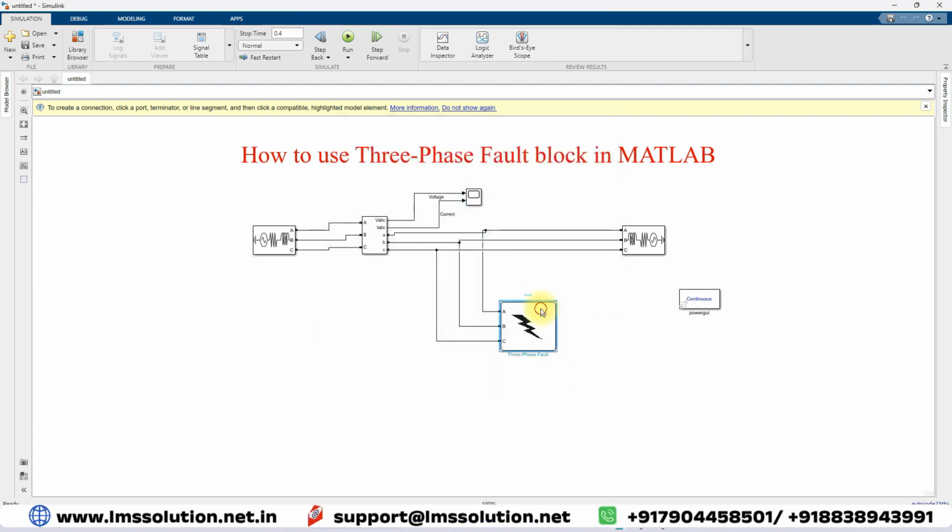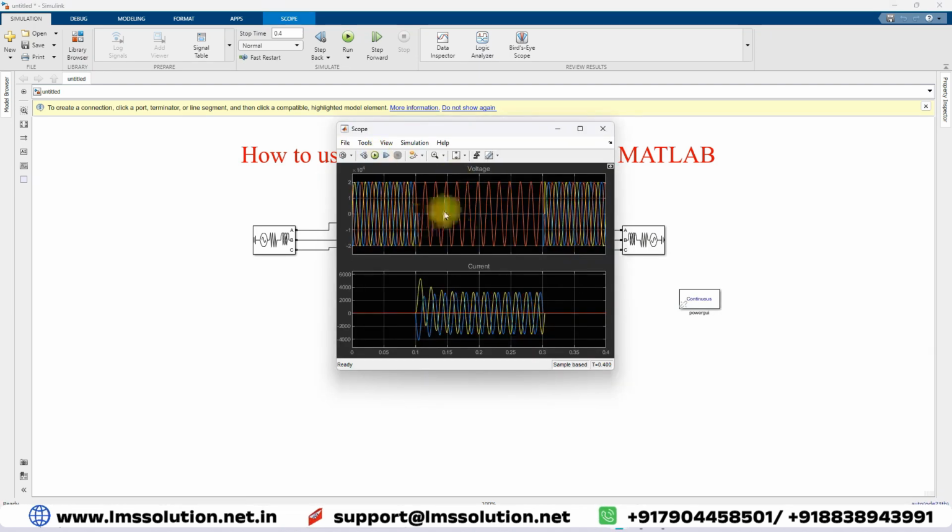Now I'm going to create a double line to ground fault and check the result. Now we can see that the two line voltages go to 0, and the remaining line has voltage. Because the lines are grounded, their voltage goes to 0. And because of the double line to ground fault, the remaining line has the normal current, and the faulted lines have current around 4000 amps. This is the fault current.